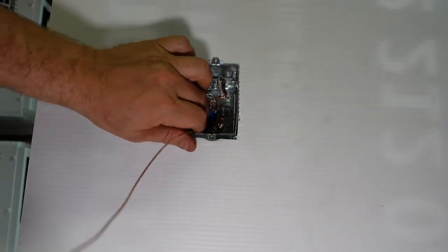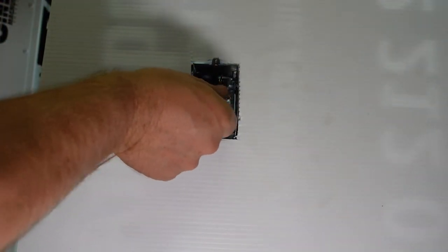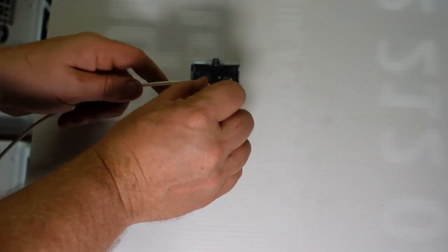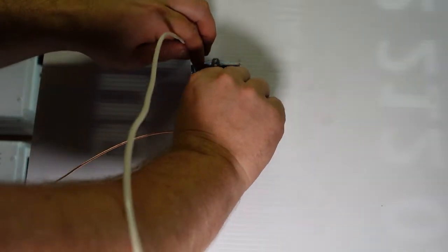Then we're going to repeat the procedure. We are going to take our white wire that we have stripped and we are going to strip it back with our strippers. Line up our white wires. We're going to put a bend on the end of the white pigtail, what we call it. We're going to line them up the best we can inside the box. This is where we usually get fingerprints on the client's wall, which they don't like, so we clean that off. And then we're going to twist them. We're going to get them in there and we're going to twist them together. This part can be sometimes difficult. To get it lined up just properly.